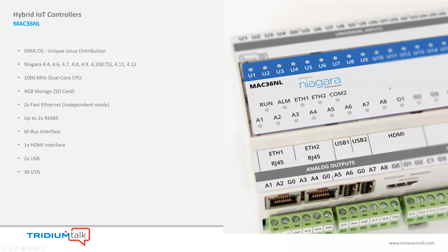The flexible licensing starts from 100 proxy points and goes up to 1,250 points. Point upgrades start from 50 points, and the 36 local IOs are pre-licensed without regard to the base capacity of the controller license. The licensing process is as expected from a Niagara controller, so licenses can be managed using Niagara Central and downloaded using the Workbench License Manager.